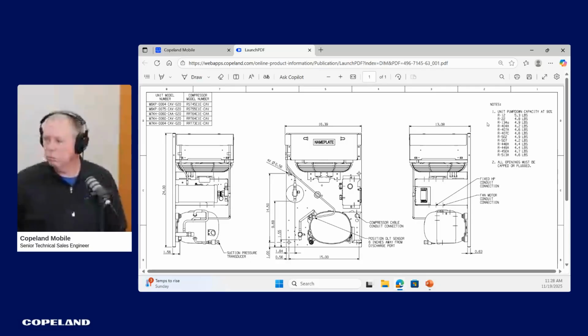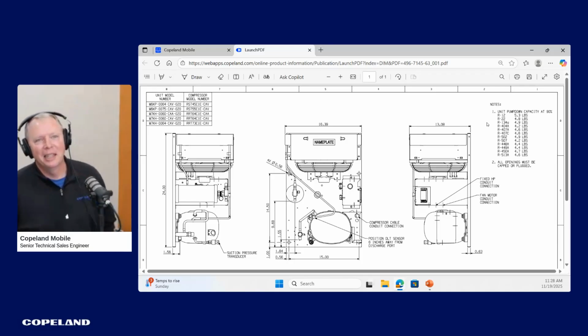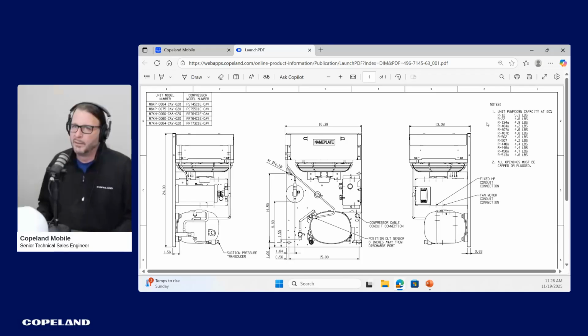Yeah, just to add to that, this is a very common question that comes in on our service line, probably on a daily basis: I have this condensing unit, what refrigerant's in it? As James mentioned, there's really no way for us to identify the refrigerant, but I could tell you what refrigerants it's used with, and the capacity, as James mentioned, of the condenser coil and in this case the receiver on this unit. So when the unit goes into a pump down cycle and all the refrigerant is forced from the low side into the high side, the values shown on the top right, based on the refrigerant you're using, is what those vessels will hold. So a very commonly asked question, and this is something that's right at your fingertips on Copeland Mobile.